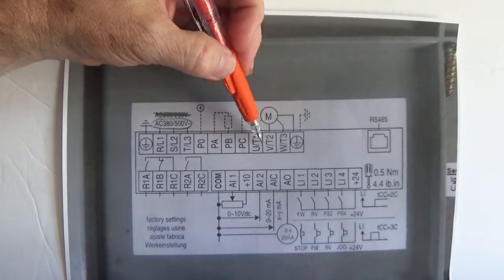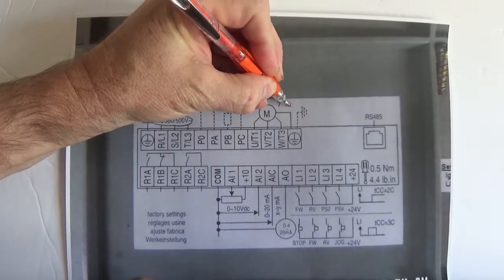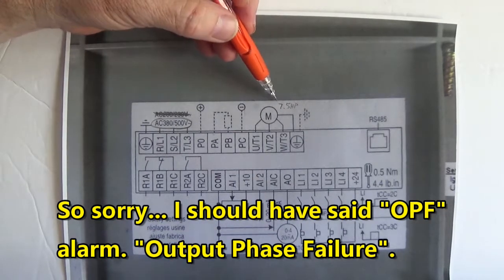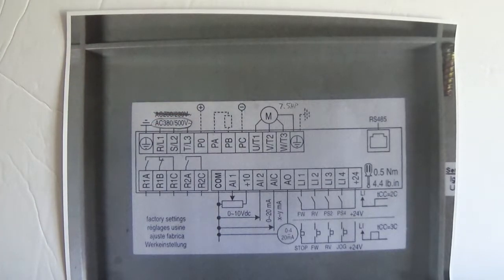Now on this drive you got to have a motor — it's a seven and a half horse motor at a minimum, otherwise you get that OPF alarm — output phase failure alarm. If you put a 1.5 horsepower motor on this drive, you'll get that OPH alarm. And Altivar does that. I've very rarely seen a drive that would fail if the output wasn't hooked up. This is the only drive I've ever worked on that would give me that alarm — they're pretty thorough about that.